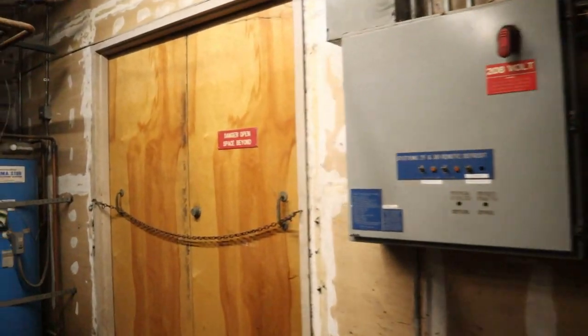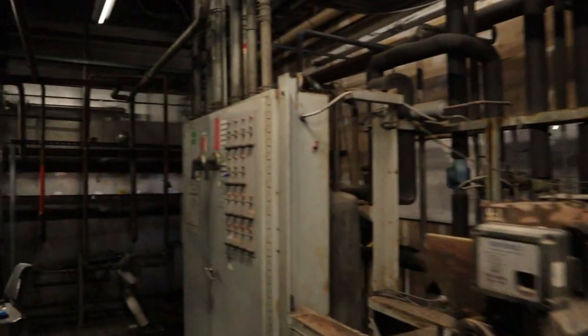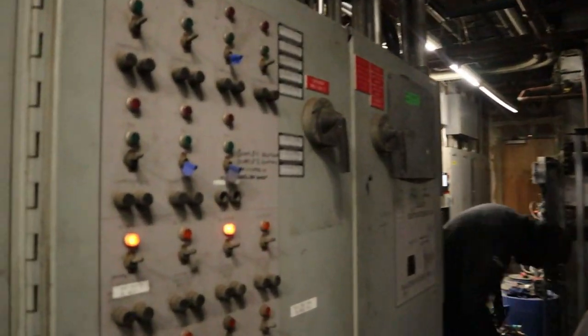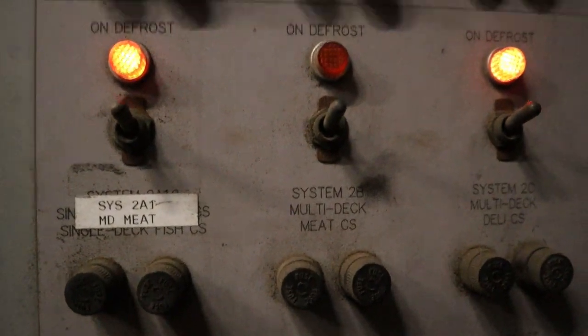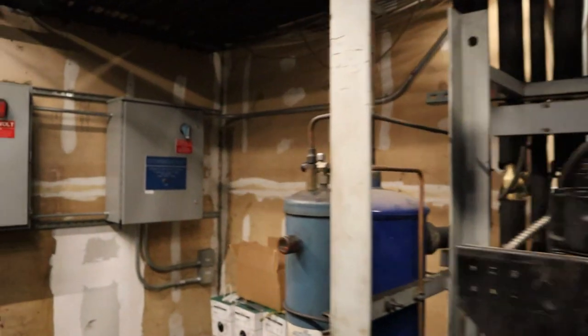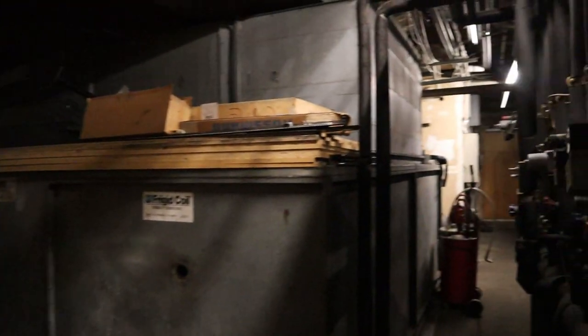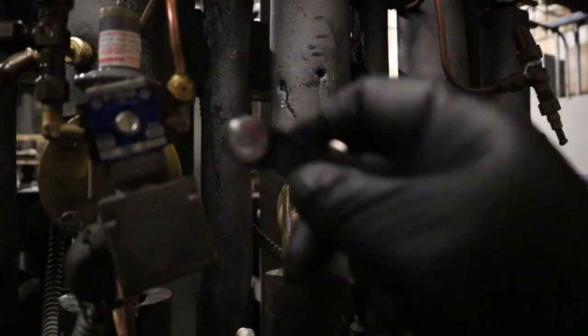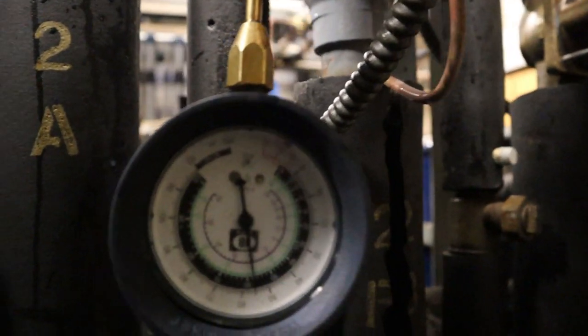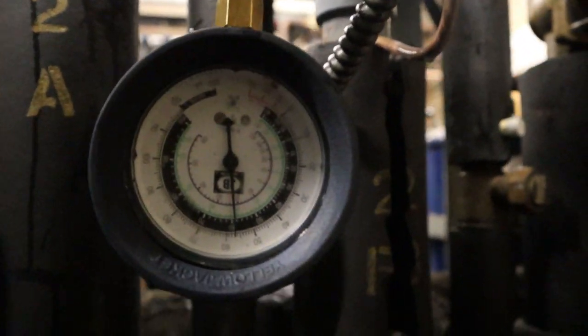Now we have to make sure the valve holds. Right now it's energized. Gonna go shut it off. Turn 2B off and make sure the pressure rises. So when it goes into defrost, I don't want it to bleed by and all the cases just isolate. Turned it off, pressure is rising as you can see. We're all good, it is holding pressure.